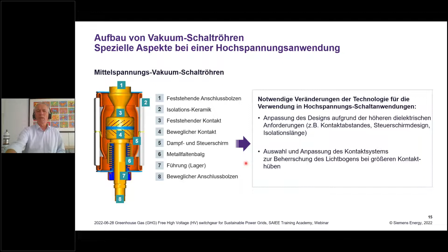Looking on the inside, once you start switching, you see on the right-hand side, we have simulation programs showing how the magnetic field is actually working in the contact system. And you see that it's very important to achieve a so-called diffuse arc mode. That means that the energy is flowing and completely spreading over the whole area which you see here. So this is a perfect vacuum interrupter switch, and that's what we developed over the years, based on the medium voltage technology, further into the high voltage technologies.